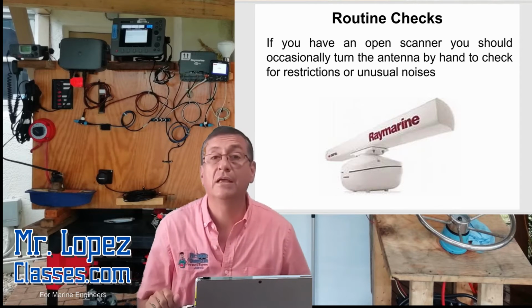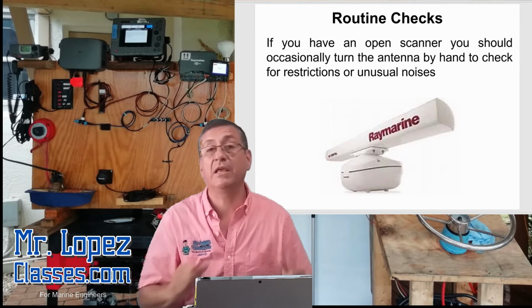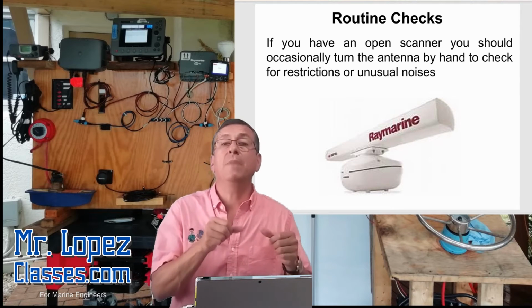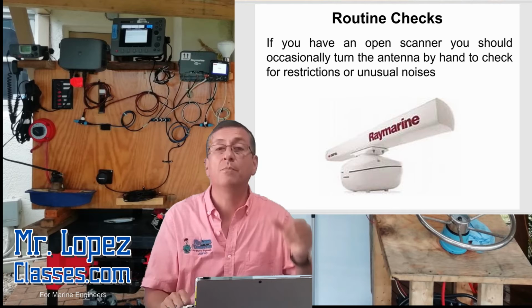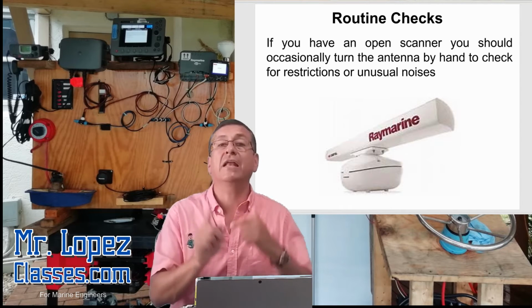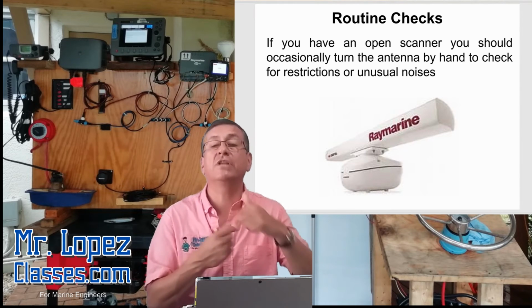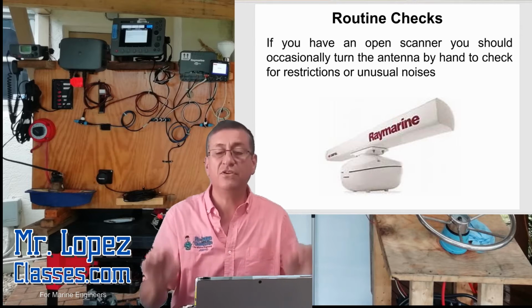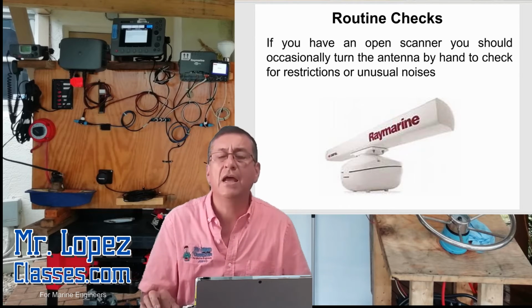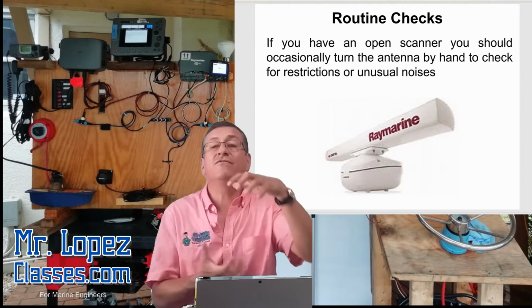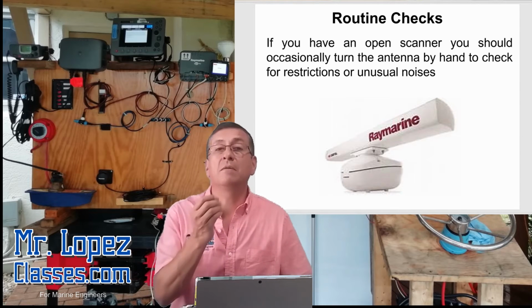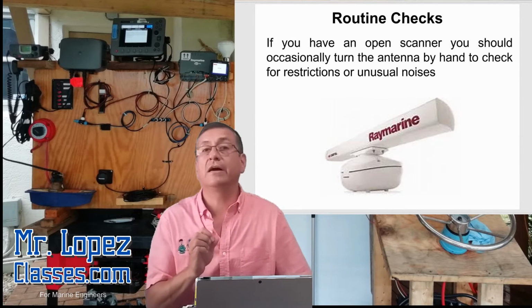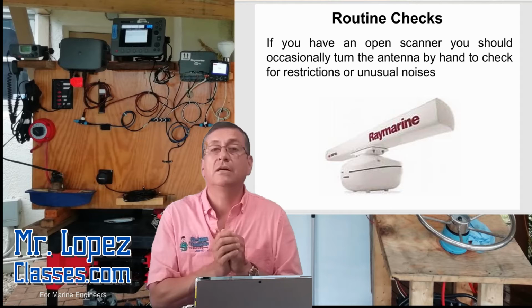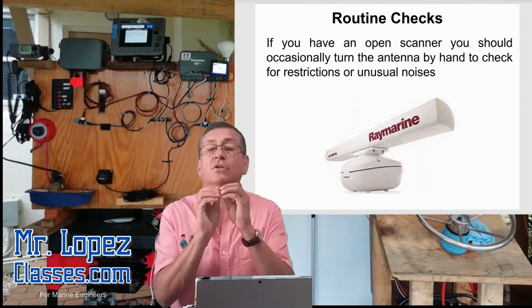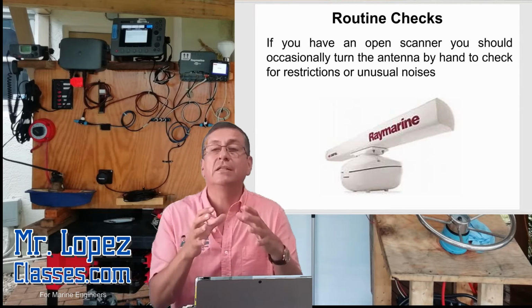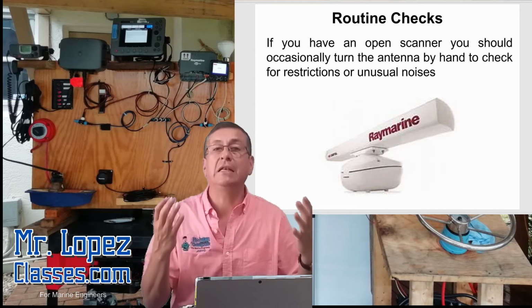I recommend you open the scanner like I explained before and verify that the belts are in good condition, properly tense, and the mechanism is turning in both directions easily. This is very, very important. And verify that inside of that box you don't have geckos, you don't have any animals, any dirt. That area should be completely clean.